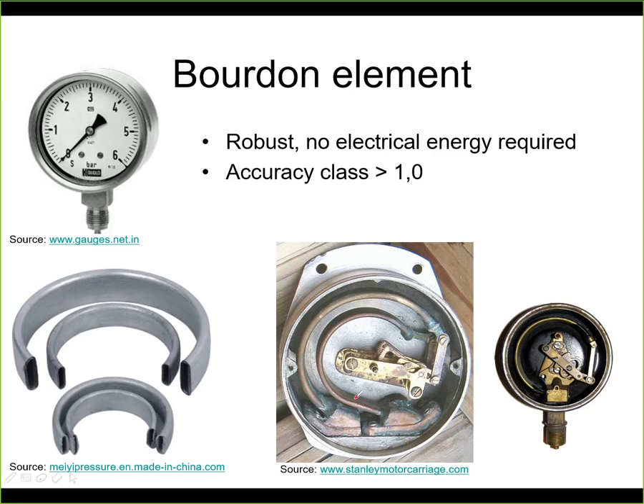and here we see a Bourdon tube inside of the instrument. Now this instrument is a little bit special because it has two Bourdon tubes. This is an instrument to measure differential pressure. But anyway, here you can see this end, the sealed end, and through those levers it is connected to the needle. And here we see those gears that transfer the actual motion to rotation of the needle.